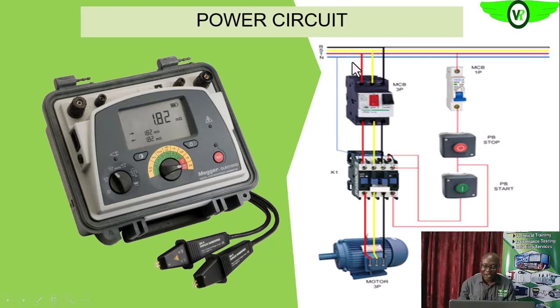So how we do it is that once you have the motor connected like this, you can test between, once you have this circuit breaker open and your contactor closed, or you can come to the contactor end, because basically these two are closed in the MCC. Then from here to here, it is the cable supplying from the MCC to the field where we have the electric motor.